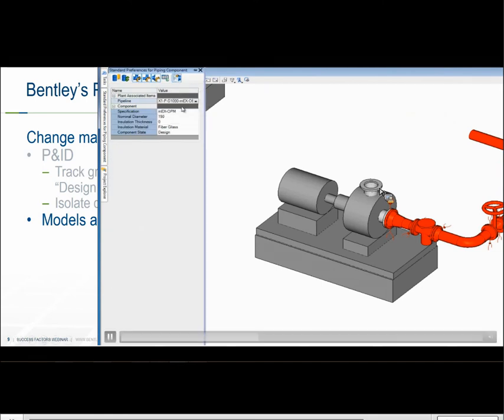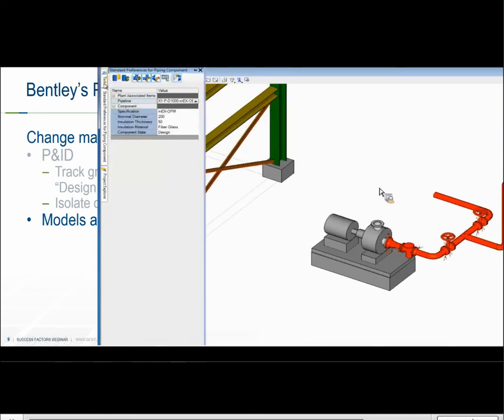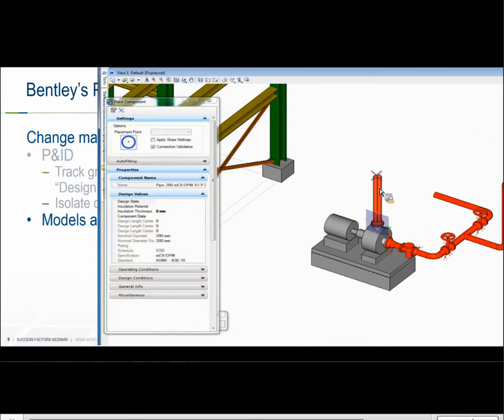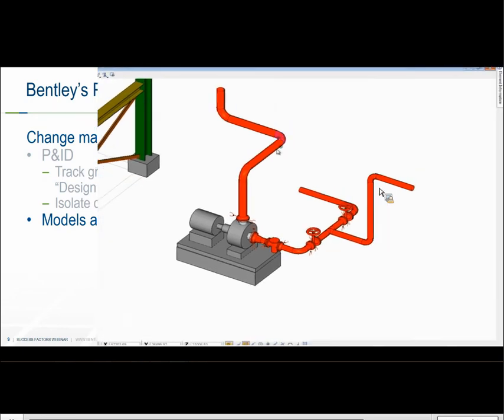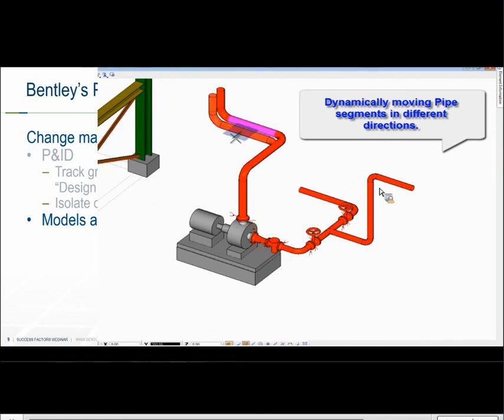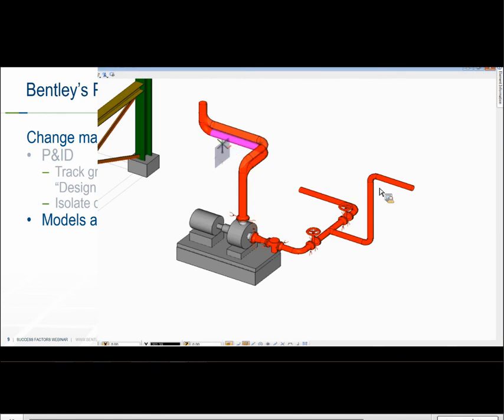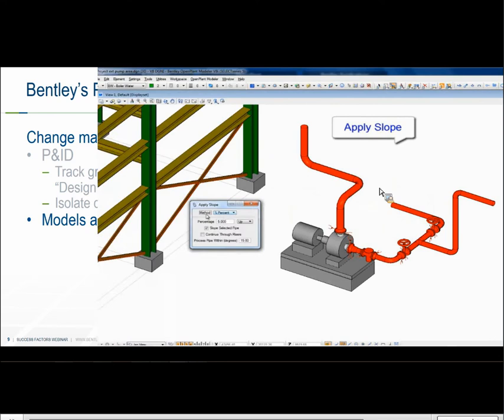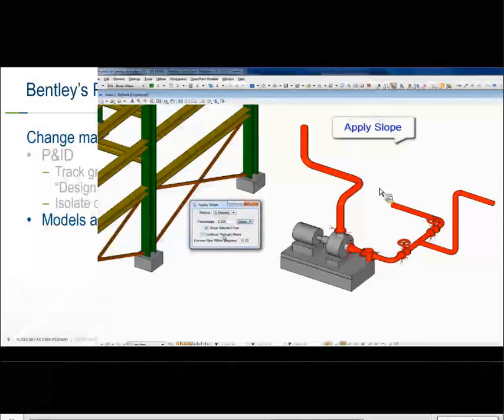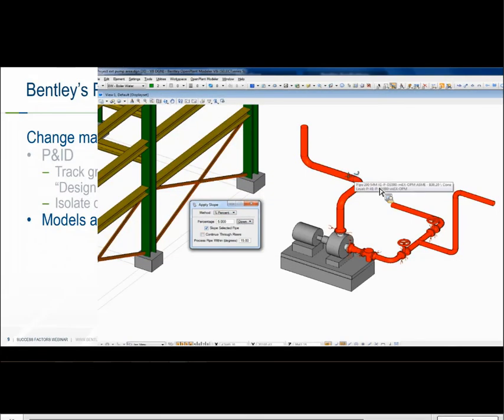After we route another line here, we'll interactively edit the line because the reality is we'll need to massage the design after it's originally placed. Notice the appropriate flange has made it to the nozzle — it's reading the data off of the intelligent nozzle. Now that we've got the routing, we can select different sections and just drag them to where we need them to go, keeping everything connected. There's also a feature to apply or reapply a slope after it's been routed, and it can be edited using that dialog.